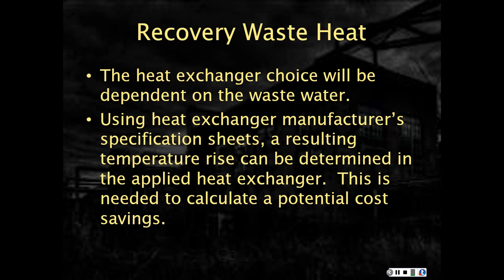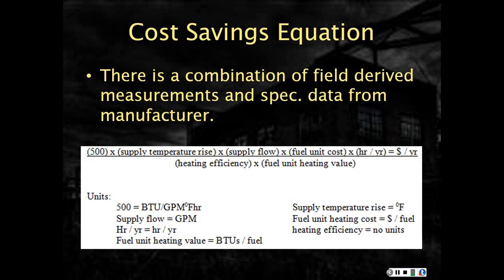This temperature rise off the heat exchanger is needed to calculate a potential cost savings. Now, there's a combination of field-derived measurements and spec data from the heat exchanger manufacturer within this formula. If you look at the base formula, it's really the heat transfer for a fluid, specifically water. So it's BTUs per hour, which would be 500 times the delta T times your flow rate, the GPM. And the rest of it should look familiar. You're going to have a fuel cost, and the number of hours per year that the process is in operation, divided by the heating efficiency for that hot water in the process to start with, and how many BTUs are in the particular fuel that is being purchased.